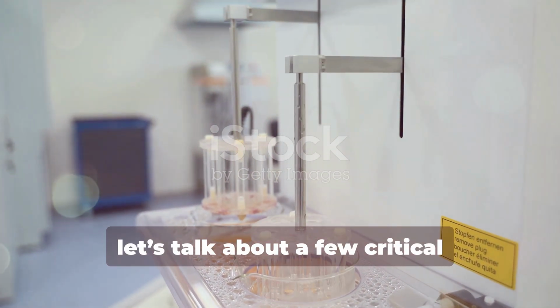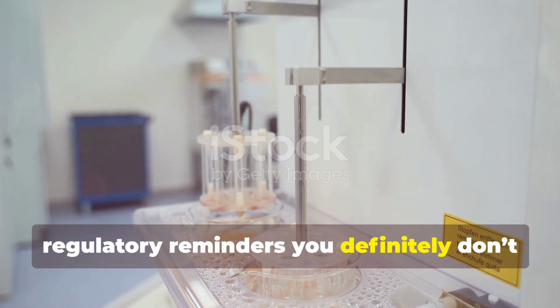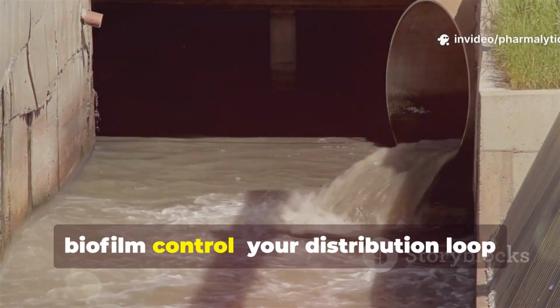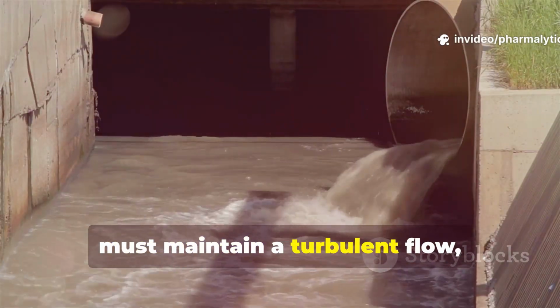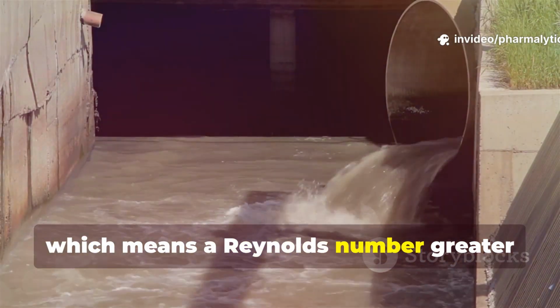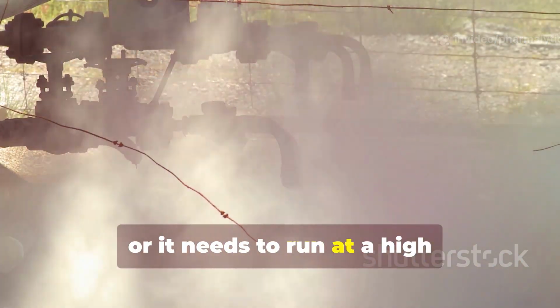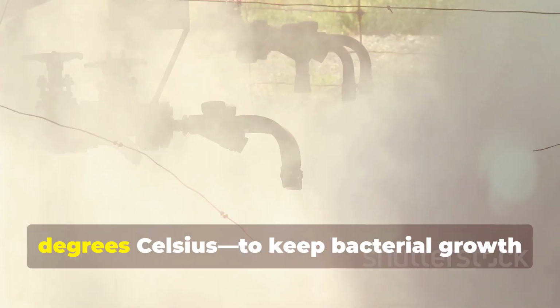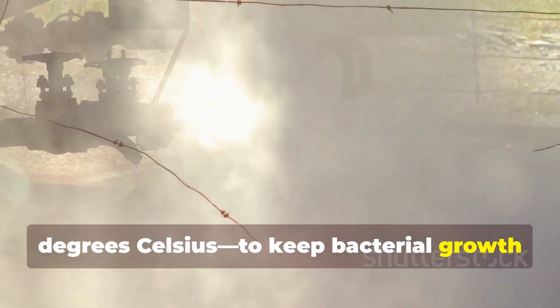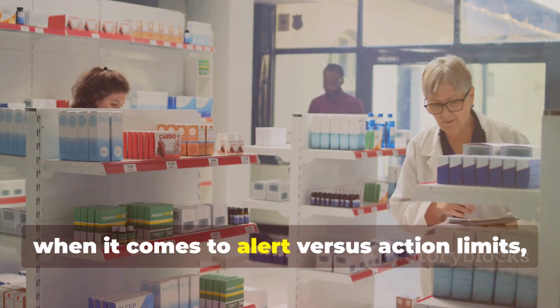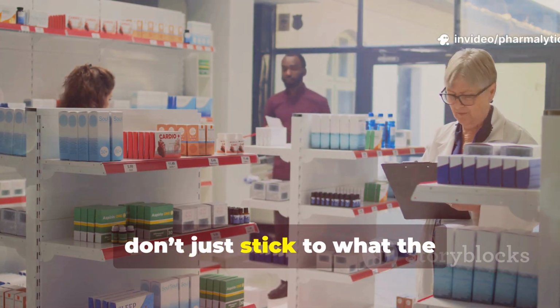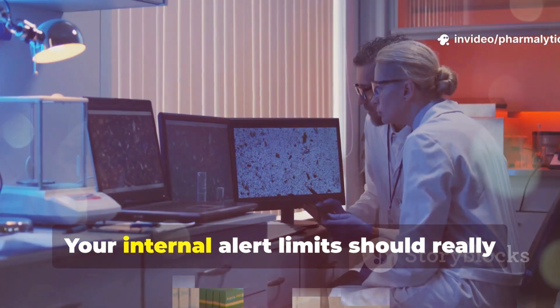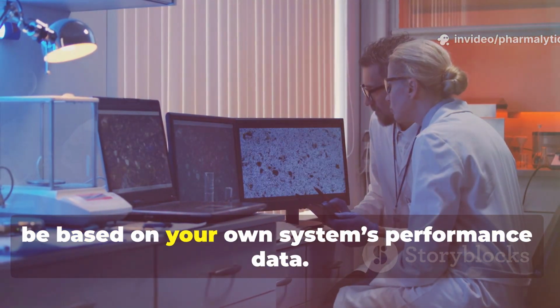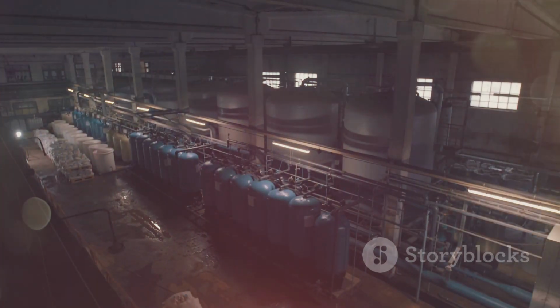Now, let's talk about a few critical regulatory reminders you definitely don't want to miss for your audit. First, biofilm control. Your distribution loop must maintain a turbulent flow, which means a Reynolds number greater than 4,000, or it needs to run at a high temperature, typically above 70 degrees Celsius, to keep bacterial growth in check. Also, when it comes to alert versus action limits, don't just stick to what the Pharmacopoeia says. Your internal alert limits should really be based on your own system's performance data.